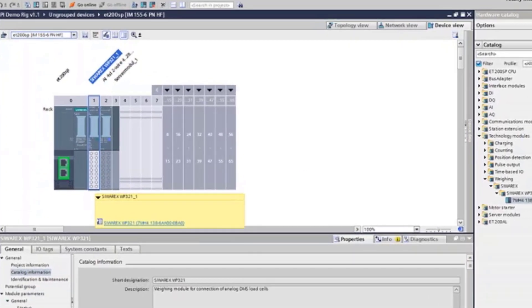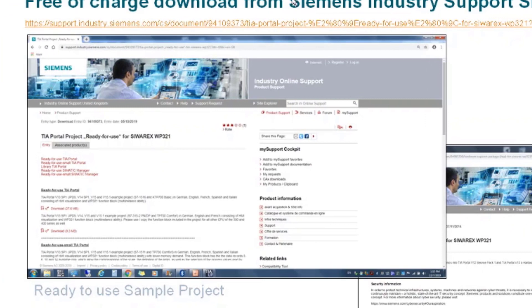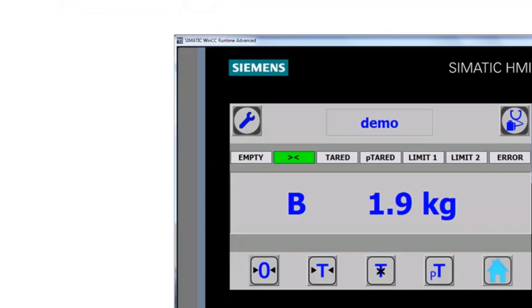In this project I have an S7-1500 PLC with an ET200SP, and integrated into that I have a WP321 weighing processor. This has already been configured by bringing the WP321 as a technology module from the hardware catalog and inserting it into slot one. We've also downloaded the WP321 ready-to-use sample project — free of charge from the Siemens Industry Support website — and integrated that into our project. That brings in the function blocks, pre-configured programming, configuration screens, and display screens, all pre-configured to reduce engineering time.